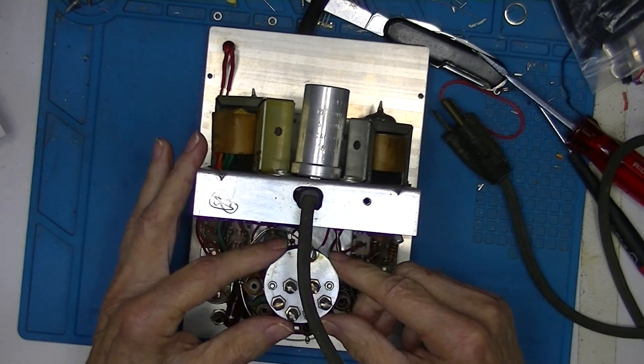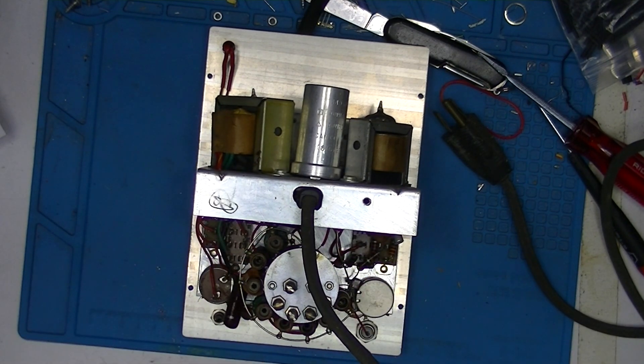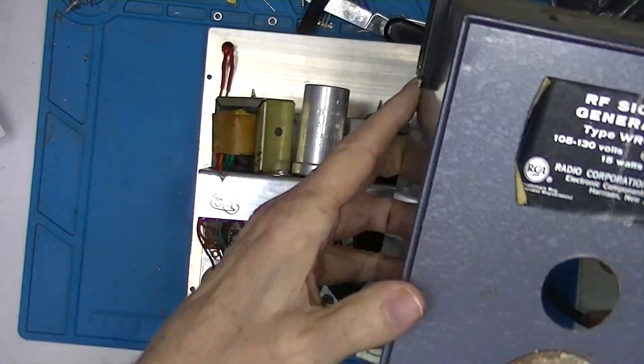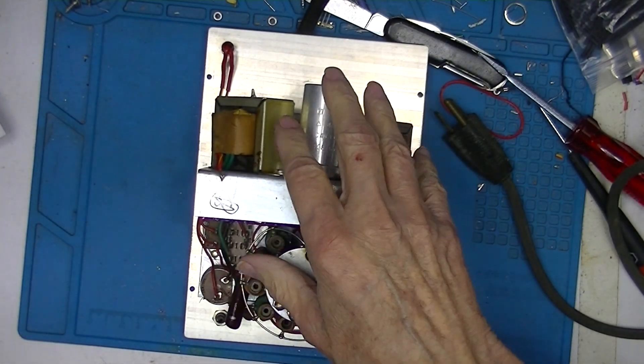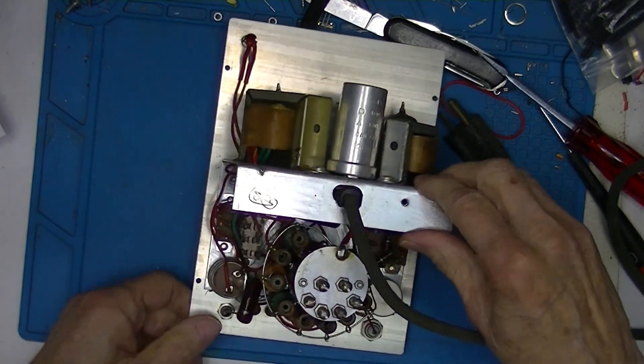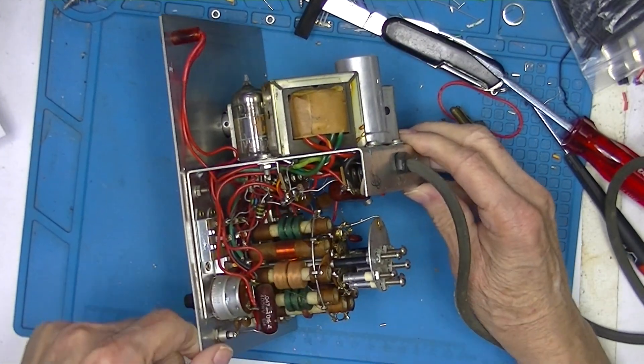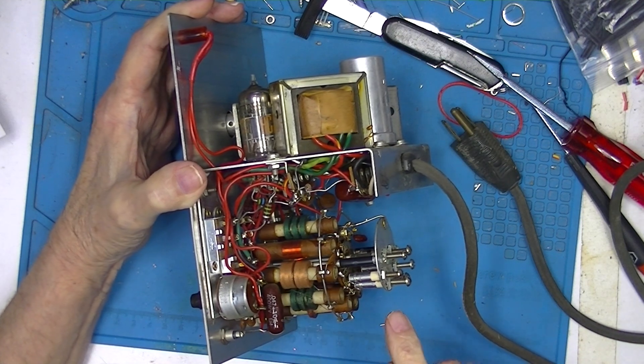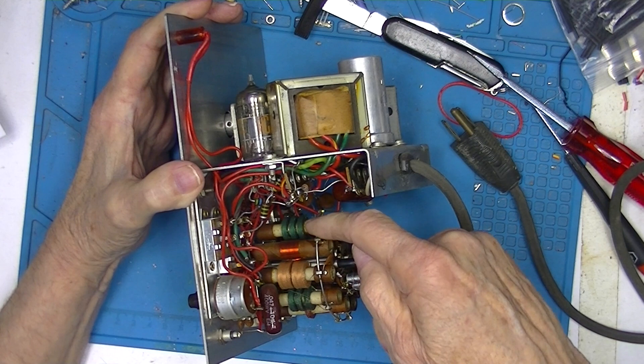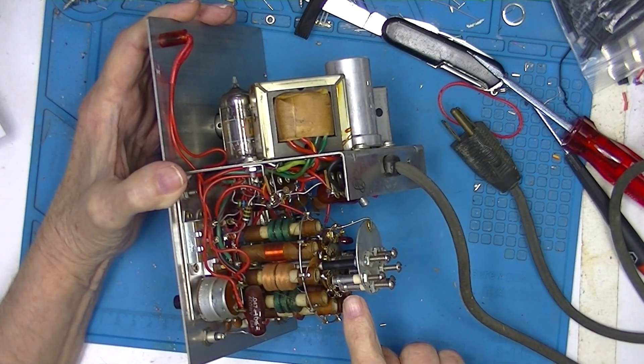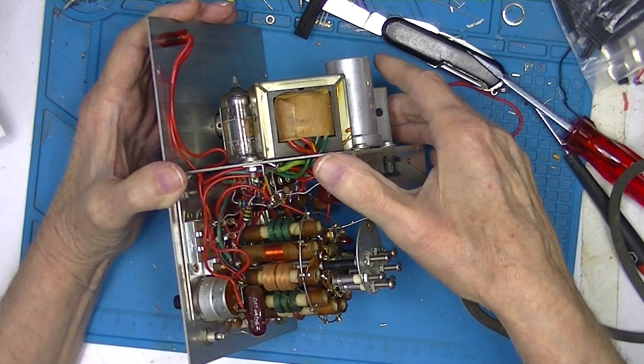This calibration can be performed with the case on. That's why we have this big plate that we can remove here at the back that will give us access to these coils and these capacitors. These are various coils, that's probably the lowest frequency and that's maybe the highest. And these are trimmer capacitors for fine adjustment. The actual tuning is done by a capacitor here.